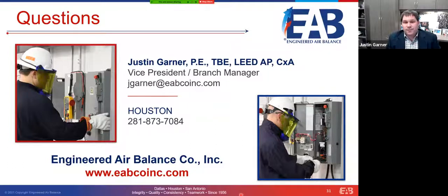What I tell the folks that work in our company and anybody else that really asked me this question is, we as TAB professionals have an obligation to measure and verify as much data as we can in the field, okay? And so yes, we can take that data off that drive if we have no other way to do it. And there are manufacturers and drives out there where you may not be able to measure the amperage and the voltage downstream. You just may not have a good place to do it. And in that case, the best case may be that you could take it off the drive.